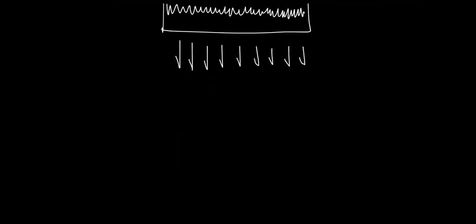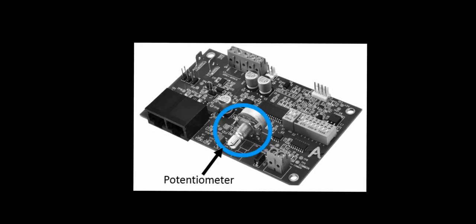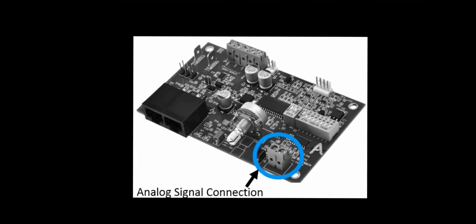The first control type we'll address for the EC units is the unit mounted control card. This is a universal control card and allows for units to be controlled in three different ways: standalone operation, controlled by a remote analog signal, and over a building management system. In standalone mode, the onboard potentiometer is used to set airflow. Clockwise rotation is used to increase airflow and counterclockwise to decrease airflow. Analog mode allows the universal control card to set airflow using a remote 0 to 10 volt signal. The signal is directly proportional to the 0 to 100 percent PWM signal controlling the motor.